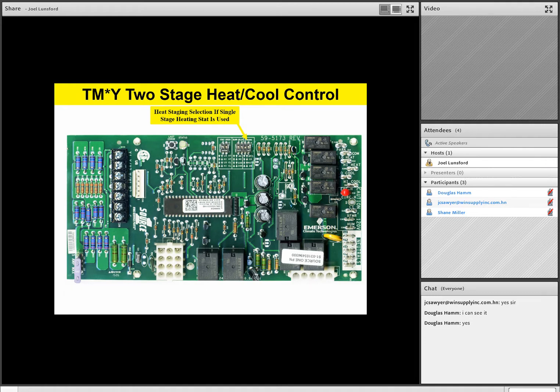In the auto position, now remember team, if you're stuck with a single stage thermostat, this auto function plugs in some intelligence on the board. The board actually starts making intelligent decisions on when to stage second stage heat. So we recommend, if you're stuck with a single stage thermostat, to make sure those dip switches are in the auto position, because then the board will make intelligent decisions on when to stage for second stage for optimal operation. It's looking at the thermostat activity, at how long it takes to satisfy the W terminal as far as time is concerned, and then it starts making decisions on when it would be a good time to stage for second stage.